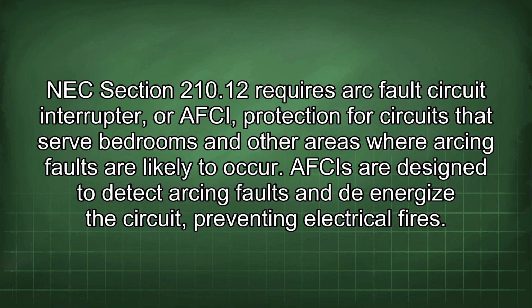NEC Section 210.12 requires arc fault circuit interrupter, or AFCI, protection for circuits that serve bedrooms and other areas where arcing faults are likely to occur. AFCIs are designed to detect arcing faults and de-energize the circuit, preventing electrical fires.